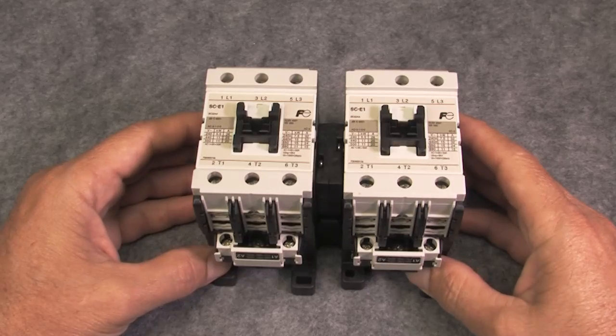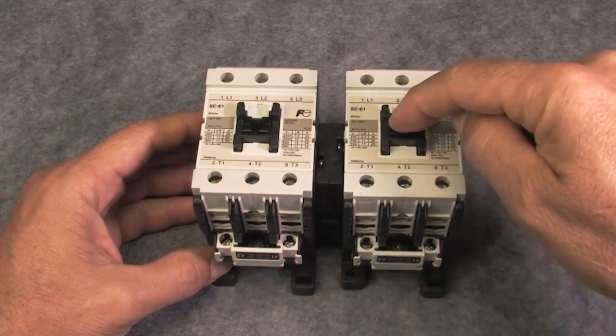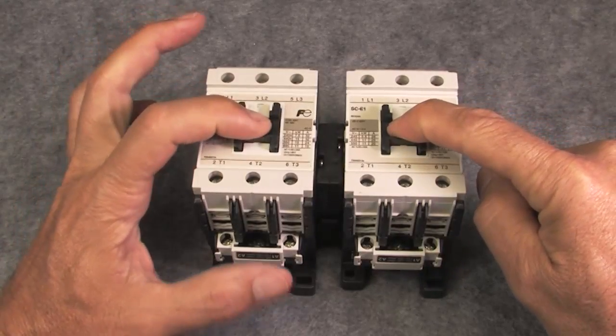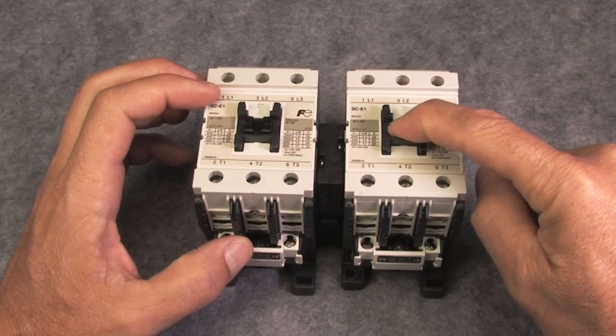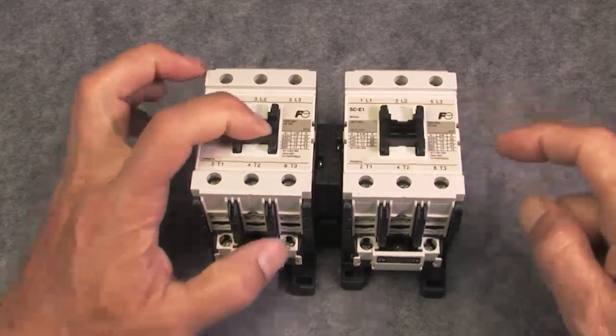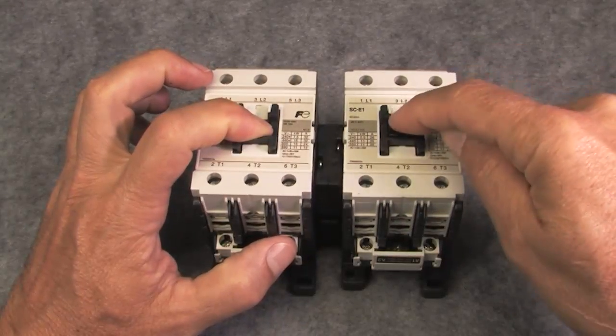This Fuji interlock module even comes with a spacer that locks the two contactors together so the interlock stays coupled to the contactors. Now, when one contactor engages, the mechanical interlock prevents the other contactor from moving. And when the other one is engaged, the original contactor can't move. Perfect.